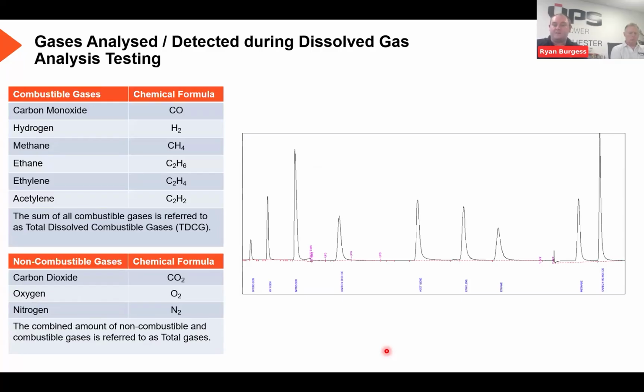So there are many gases that can be analysed through DGA. First, we'll look at the combustible gases. So you've got hydrogen, methane, ethane, ethylene, and acetylene. Carbon monoxide is classed as a combustible gas. Then you've got your non-combustible gases of carbon dioxide, oxygen, and nitrogen. And depending on the ratios and the amounts of each gas present, we can determine what kind of faults are present, such as arcing, overheating, and insulation degradation, which the next slide will explain a lot more.